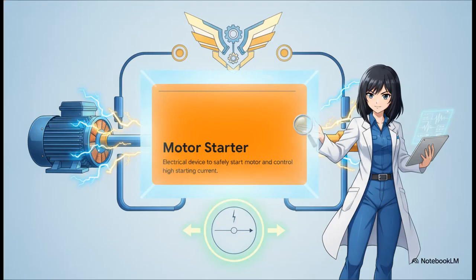So, to solve this, we bring in our hero, the motor starter. Simply put, this is an electrical device designed to safely start the motor while reining in that dangerously high starting current. If you want to protect your expensive machinery and avoid wrecking the rest of the electrical system, having a motor starter is absolutely non-negotiable.